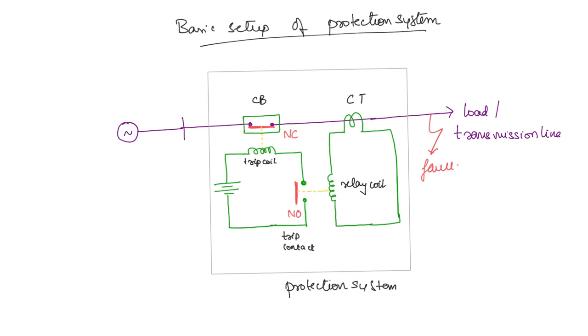Here, some important equipment that you can see in the protection system: the first one is the circuit breaker. Second, you have the trip circuit. This entire circuit that you have here helps in tripping the circuit breaker, so it is the trip circuit. That is the second important component. Next, what is the equipment that identifies the current? It is the current transformer. That is also one major piece of equipment required in a protection system. And we also have the relay coil. So these are some of the major components in a protection system, but remember we have only discussed the basic setup. Now there are a few important terms that you should know.